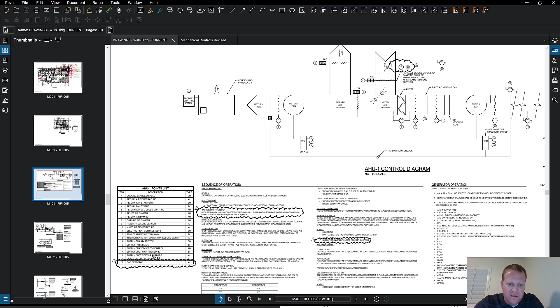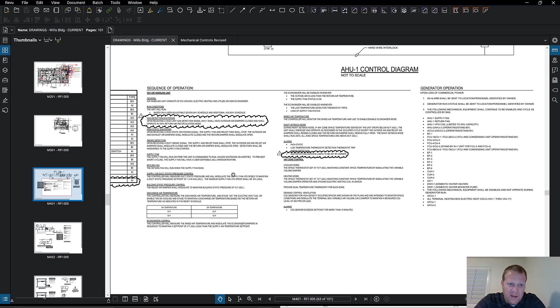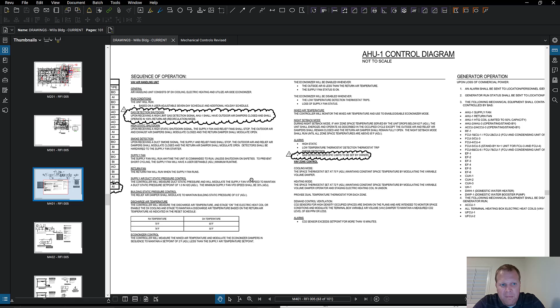We get to TAB. Now, we have the sequence of operation. I mentioned that earlier. So once we get to a point where we want to make sure the entire system is working, then there is a test sequence written by the commissioning agent that's going to test to make sure that the sequence of operation is actually working. So do the economizers turn on under these parameters? Is the supply fan running under the correct parameters? So they take the sequence of operation and say, okay, what is it saying that the equipment's supposed to do? And then they write a test to try and make sure that that can be done.